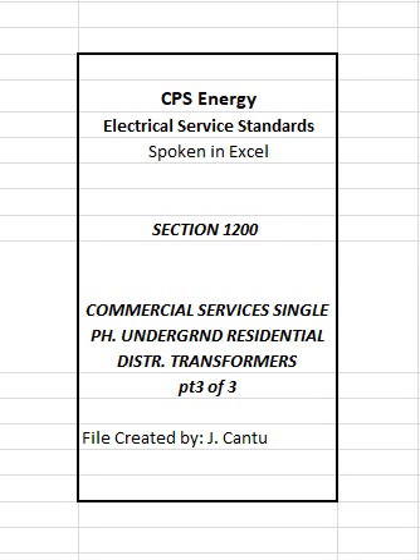1205.3 Service conduits. The standard conduit installation requires the use of Schedule 40 or 80 PVC conduits. The quantities and sizes of service conduits that may be connected to CPS Energy transformers and secondary enclosures will be determined by CPS Energy. Customer shall be responsible for coordinating with CPS Energy to ensure that the number and size of service conduits required for customers' calculated loads will be in accordance with Table 1201, Note 1. Conduits are required to exit the bottom of the transformer through the slab.